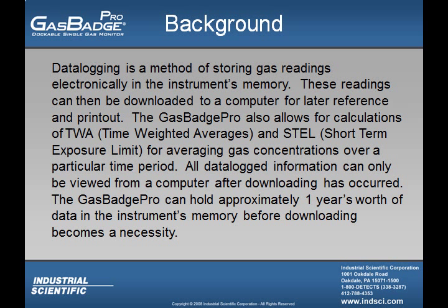Data logging is a method of storing gas readings electronically in the instrument's memory. These readings can then be downloaded to a computer for later reference and printout. The Gas Badge Pro also allows for calculations of TWA, time-weighted averages, and STEL, short-term exposure limit, for averaging gas concentrations over a particular time period. All data logged information can only be viewed from a computer after downloading has occurred. The Gas Badge Pro can hold approximately one year's worth of data in the instrument's memory before downloading becomes a necessity.